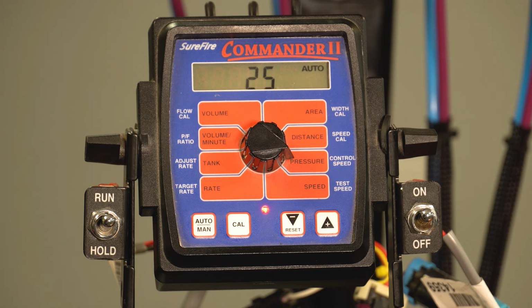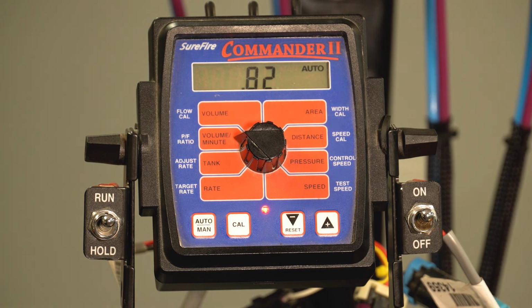And with our Tower electric pump systems, we want to be running anywhere between 15 and 30 PSI comfortably. We can sure run a little bit higher than that into the 30s, but we like to stay under that 40 PSI range for sure with our electric pump system. So we're in good shape there. Again, we can also flip over to volume per minute and check that. So we're at 0.8 roughly, and that's going to move around.